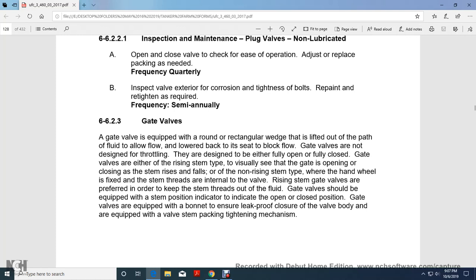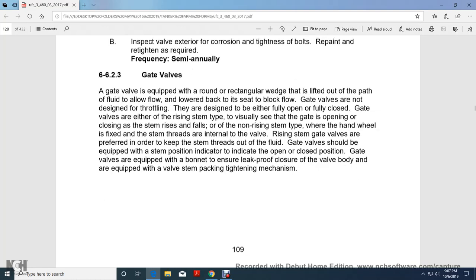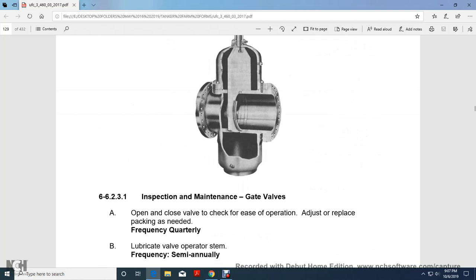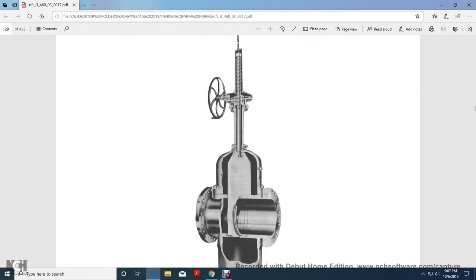A gate valve is equipped with a bonnet, and to ensure leak-proof closure of the valve body, it is equipped with valve stem packing with a tightening mechanism. And it shows a gate valve.